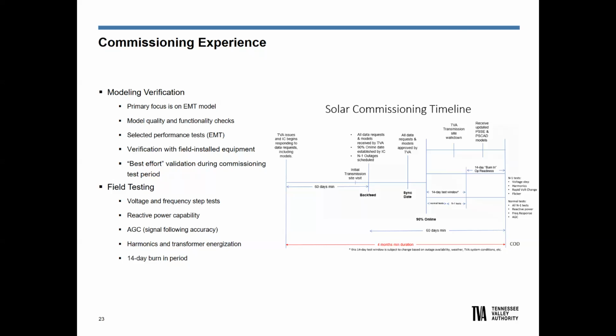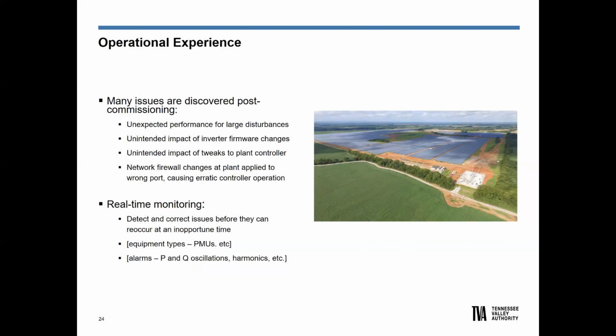Next slide. So, getting more operational experience here. Most are discovered post-commissioning, unfortunately. Unexpected performance for large disturbances: have a fault on the system, have momentary cessations, voltage dips, voltage swings. When they are going back, the controller and the operator will go back and try to modify the firmware. We see unintended consequences because of that, as well as if they're tweaking the plant controller due to performance during large disturbances, we end up seeing them go sometimes too fast on the loop control or too high on the loop control, and they end up having oscillations because of that.